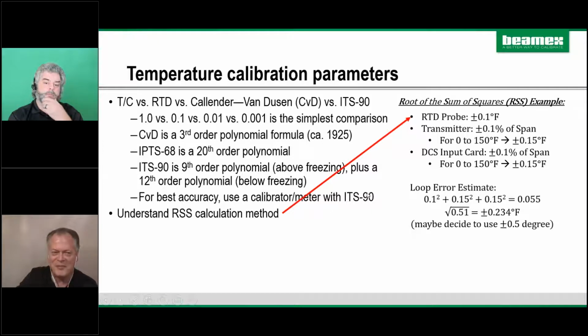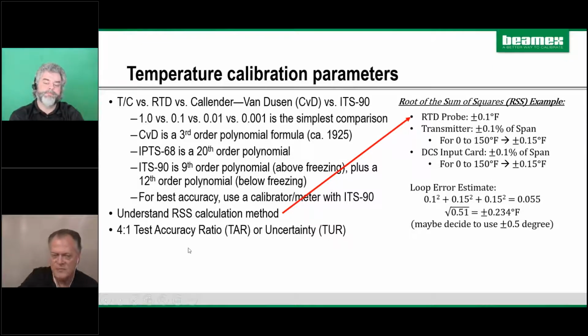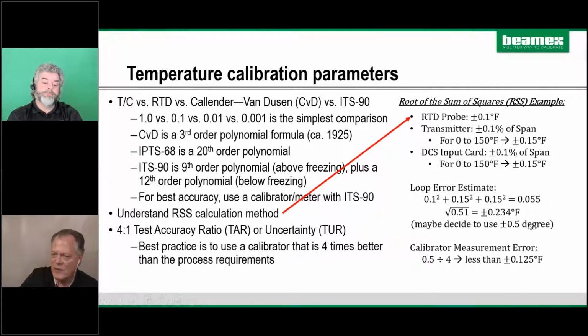But there's another factor that comes into play. I'm sure most of you have heard that you want a 4-to-1 test accuracy ratio, or test uncertainty ratio, depending on whether you're a metrologist or just looking at your equipment. In practice, best practice is to have a calibrator, or a calibration standard, that is 4 times more accurate than the equipment you're trying to test. So if we take this 0.5 degree and divide it by 4, that's the level you need your calibration equipment to be accurate to in order to test something to that level.